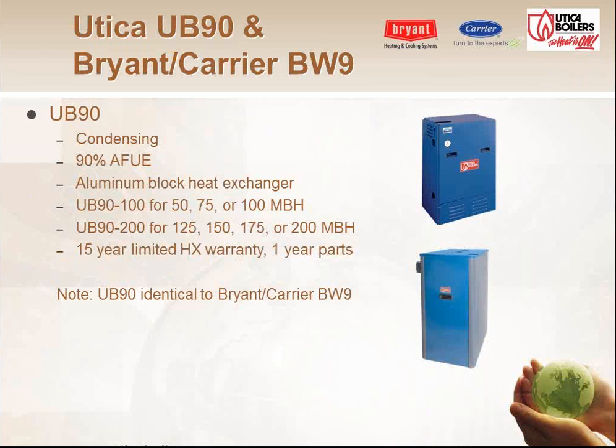All right. There's other ways we do some of these higher mass ones. This one from Utica, Bryant, and Carrier, they're aluminum block heat exchangers. So they're basically designed to mimic a cast iron block, but they're made out of aluminum, which can handle the condensate. Other than that, it looks just like a cast iron boiler. Right? They hold the same amount of water the old boiler used to hold, which is a fairly high mass, hence they don't need to have the primary, secondary piping.